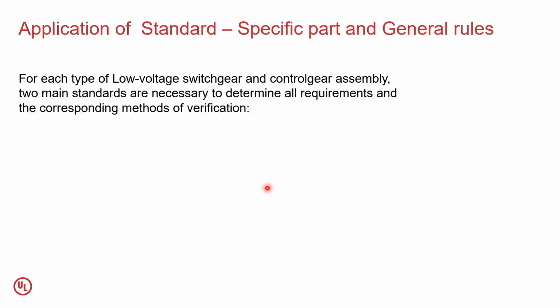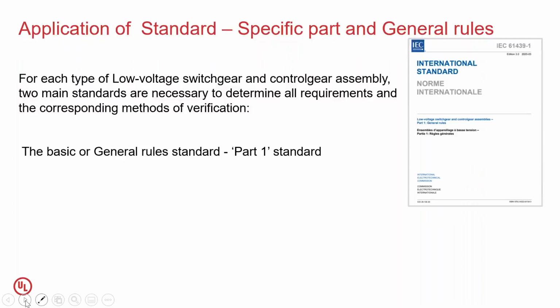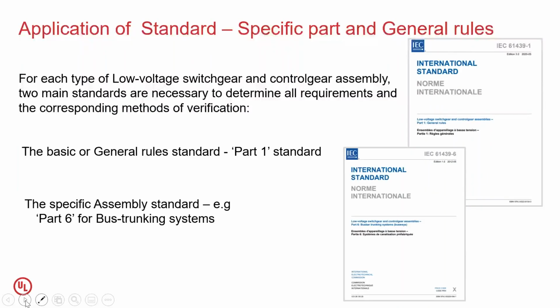Let's now move forward to how to apply the standard. Now that we know for any product like distribution boards, a panel board or a busway, you essentially need to refer to two standards, that is the part 1 and the specific part, we need to understand how they could be applied. For each type of switchgear and controlgear assemblies, there are two main standards that are necessary in order to apply all the requirements and to also ensure the corresponding methods of verification. To start with, we need the basic or the general rule standard, which I would call the part 1 standard. Then, if we talk about the bus trunking system, you need the specific assembly standard or the part 6. So you need both of them.